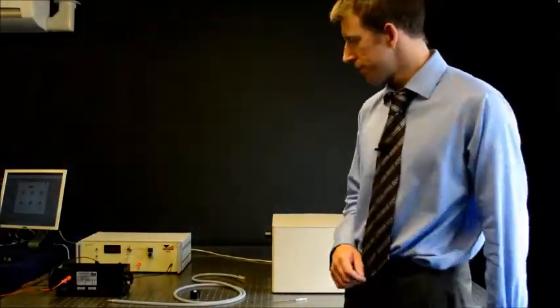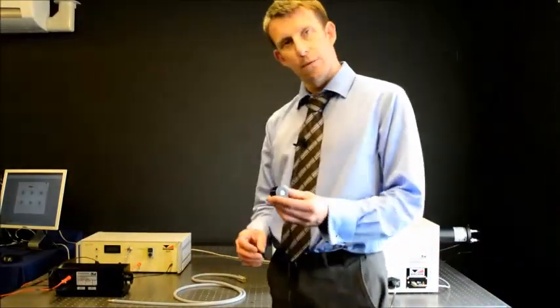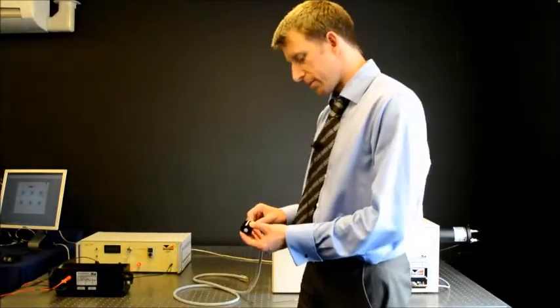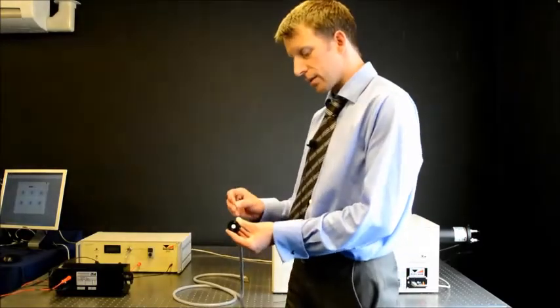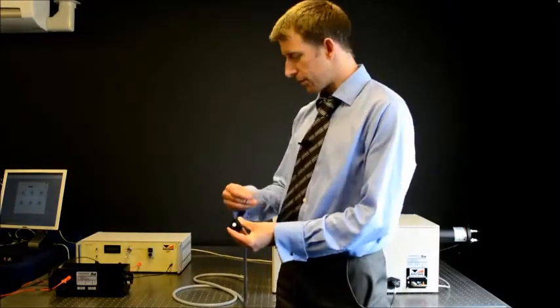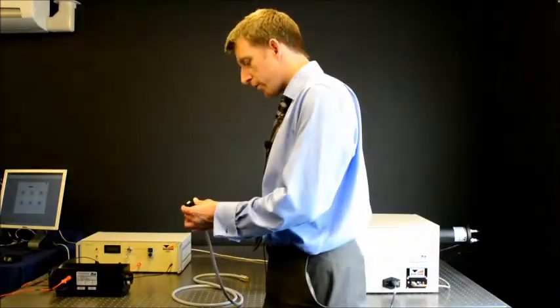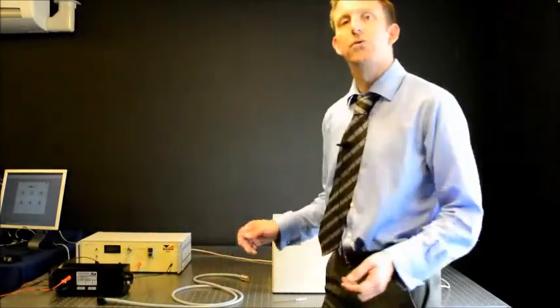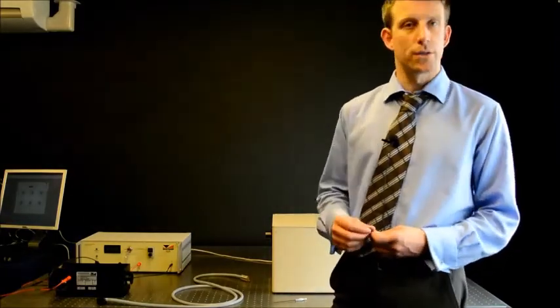In order to set the system up in the spectral irradiance mode, we should connect the D7 input optic to the quartz fibre bundle, holding it in place with the retaining grub screw. Where the fibre bundle is not already connected to the IDR300, we should go to the software and initialise this time in the spectral irradiance mode.